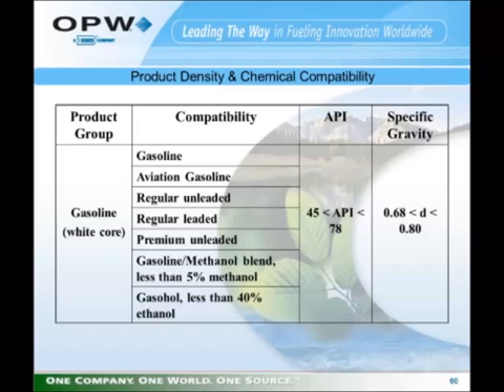The water floats are used in different API ranges. The considered application would be whether they are a gasoline water float or a diesel water float, but with different grades of diesel, the API changes, and therefore at certain points some diesel-based products are too thick to support water floats, just as some motor oils or hydraulic oils are too thick to support water floats.